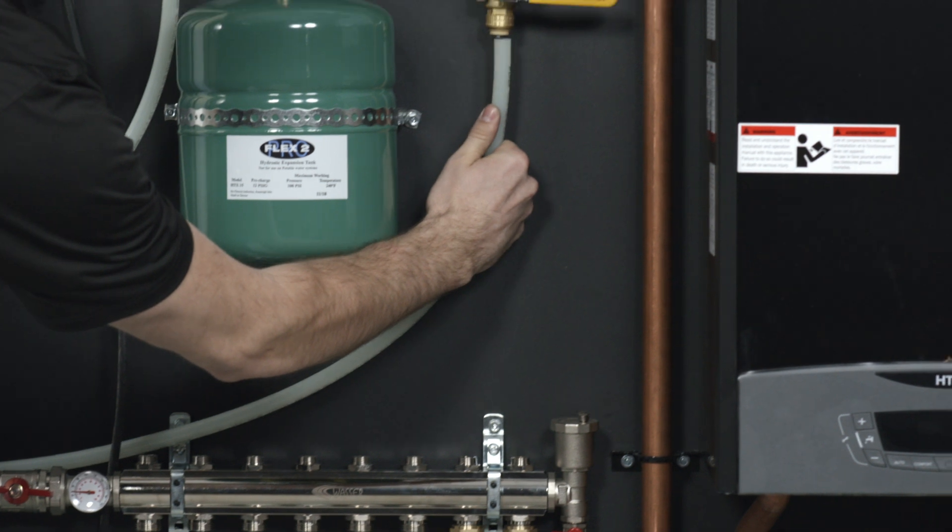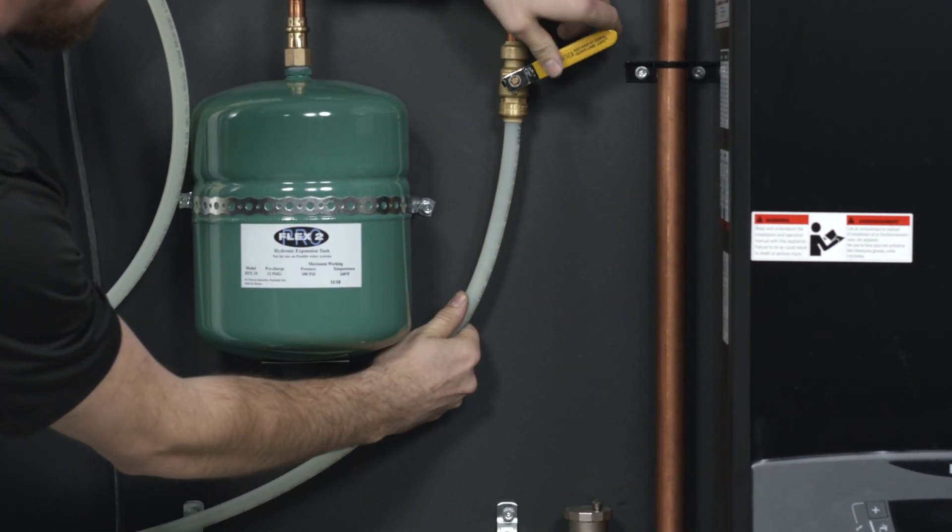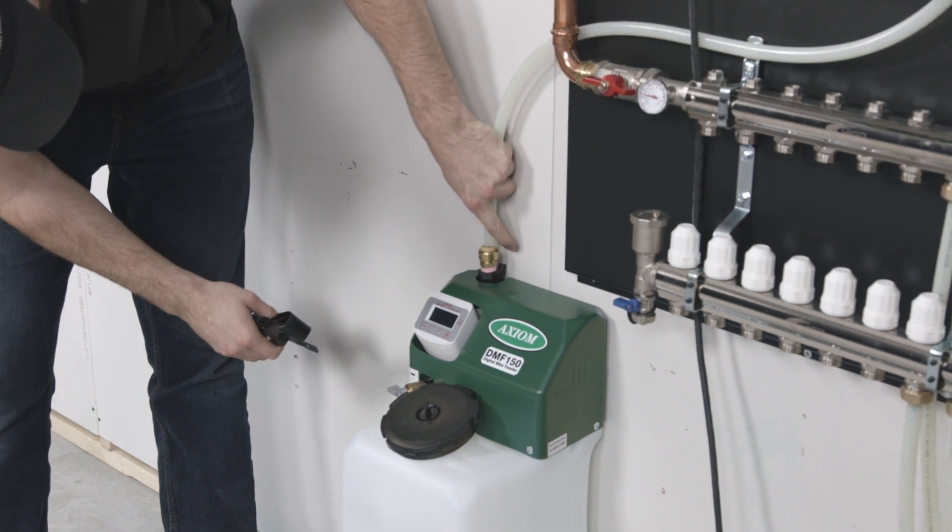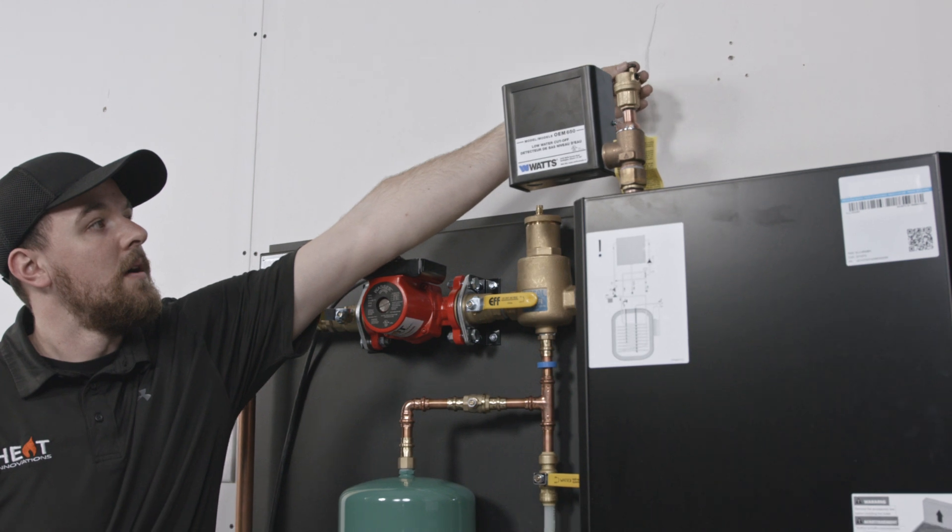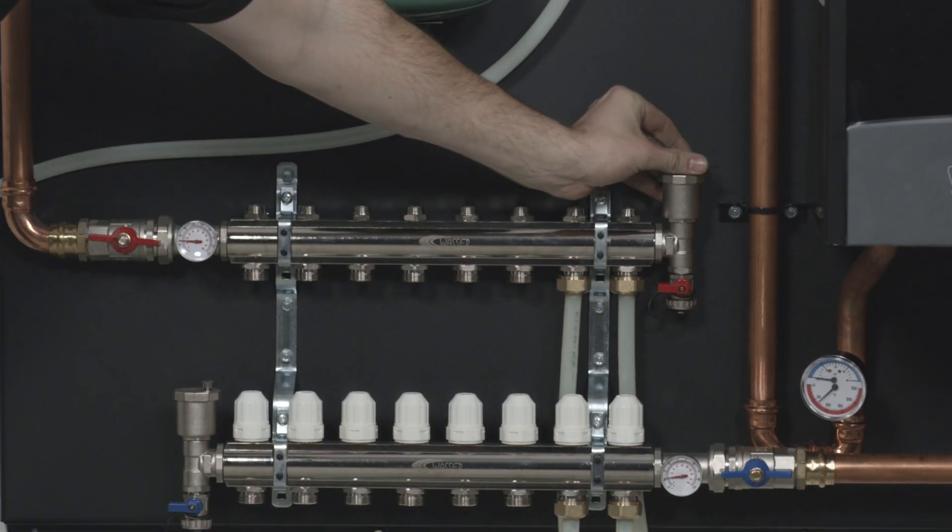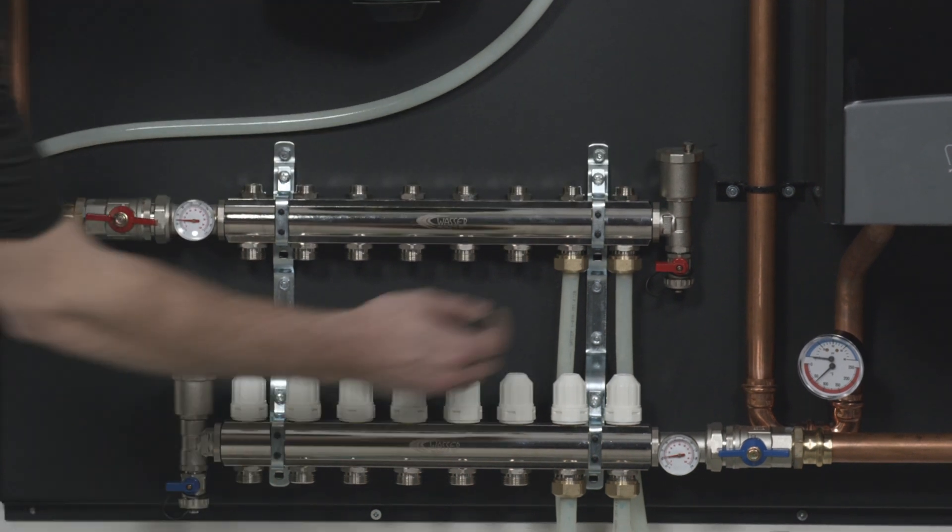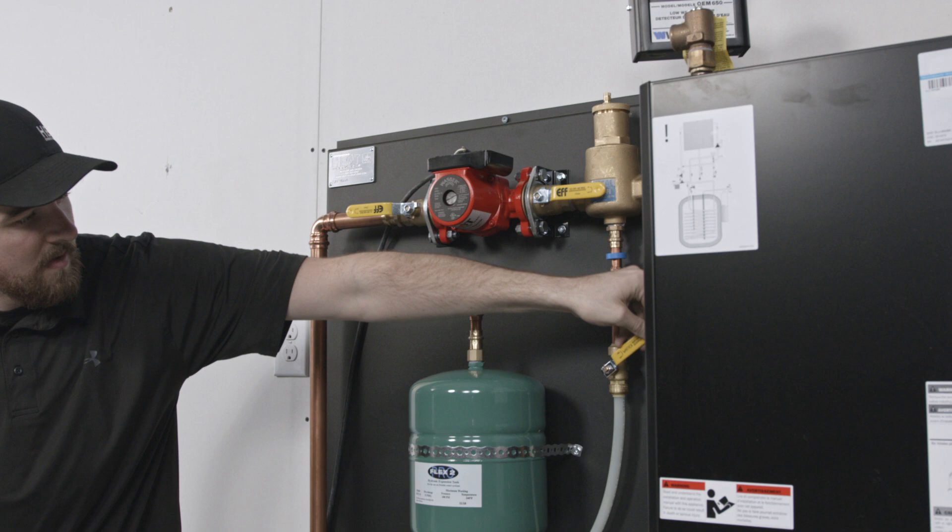Using half-inch PEX pipe or copper, connect the feeding system to the fill port between the air eliminator and expansion tank. Check to make sure all air bleeders are in the open position. Also make sure all ball valves are open to allow the system to fill.